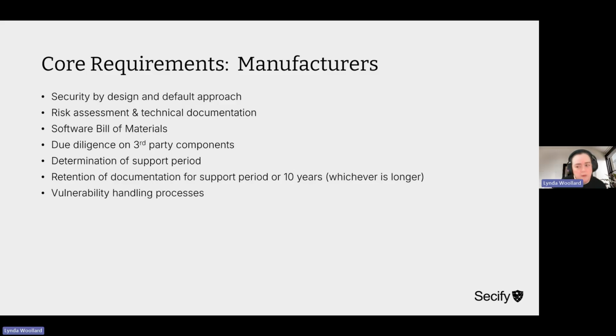You must have a clear vulnerability handling process. This is in Annex 1, Part 2, where it sets out very clear handling requirements in terms of identifying vulnerabilities, addressing those vulnerabilities without undue delay, and pushing out patches. And there are clear rules on this. So, for example, you should not push out functionality patches with security patches. They should be separate patching. So you have a lot of requirements here in terms of how you manage vulnerabilities in your products.